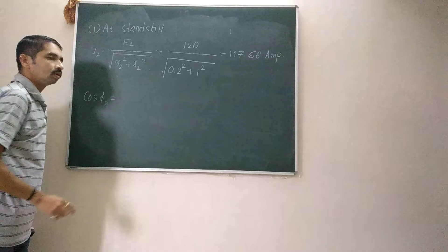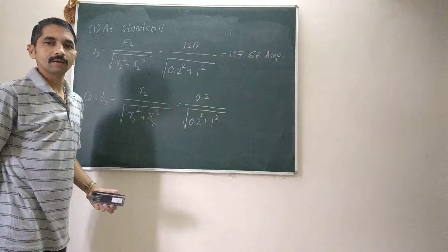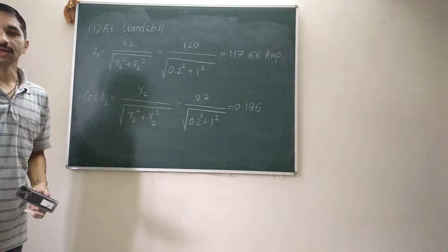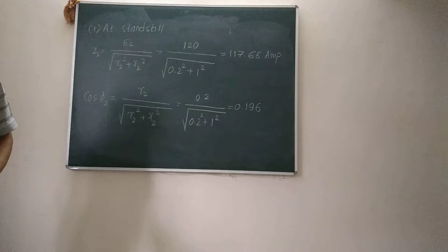Okay, if you are done with this, let us try to find out the value of rotor power factor at standstill. So cos phi 2 is given by the expression cos phi 2 is equal to R2 upon square root of R2 square plus X2 square. Once again I have to substitute the values of the given parameters. So that will be 0.2 upon square root of 0.2 square plus 1 square. If I put the values in the calculator and solve it further, I am getting the value of rotor power factor as 0.196. Please try to check this answer. If you are getting a similar answer, it is fine. Otherwise, try to calculate it again. So I am getting the value of I2 and cos phi 2 respectively as 117.66 and 0.196. So is it clear?